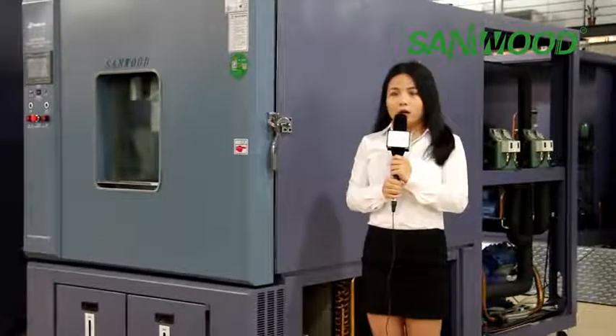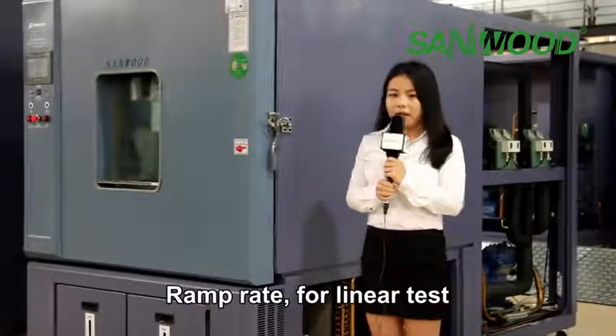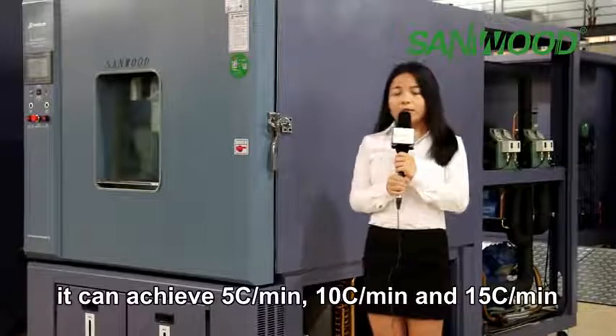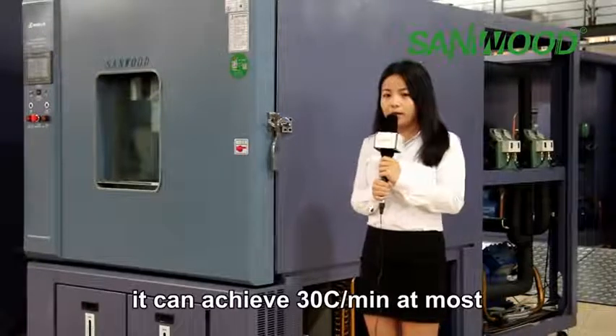For heating and cooling rate — in other words, ramp rate — for linear tests, it can achieve 5 degrees per minute, 10 degrees per minute, and 15 degrees per minute. For non-linear tests, it can achieve 30 degrees per minute at most.